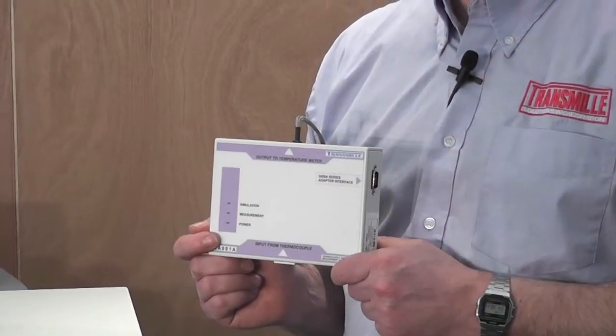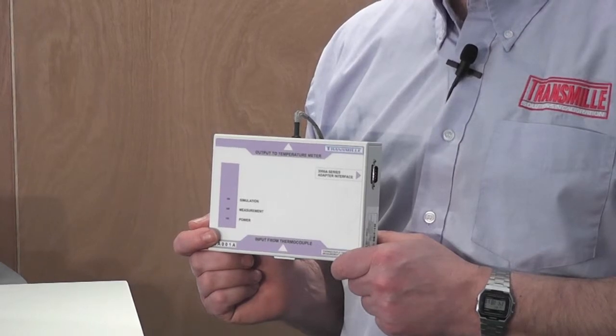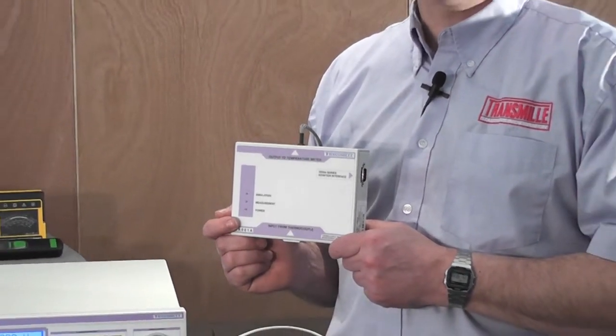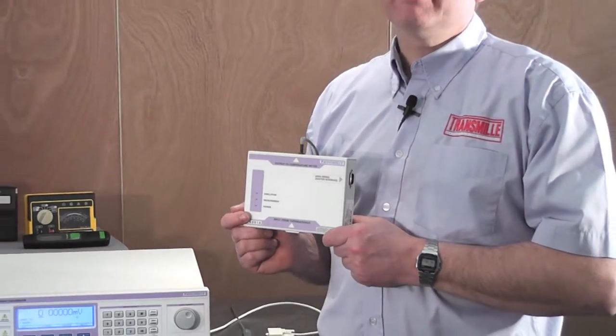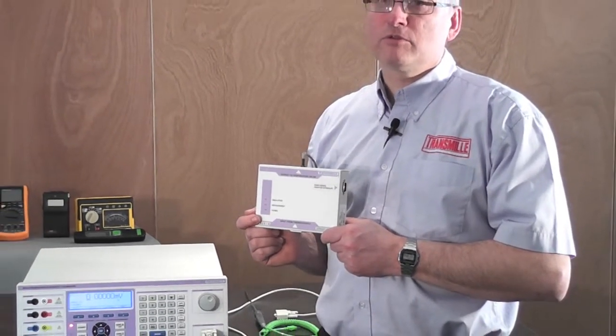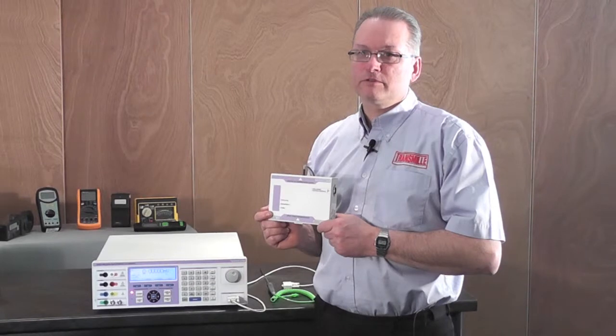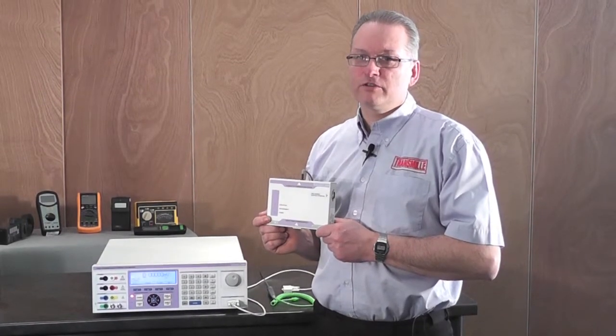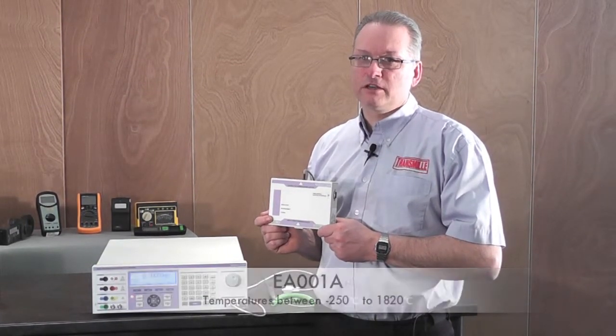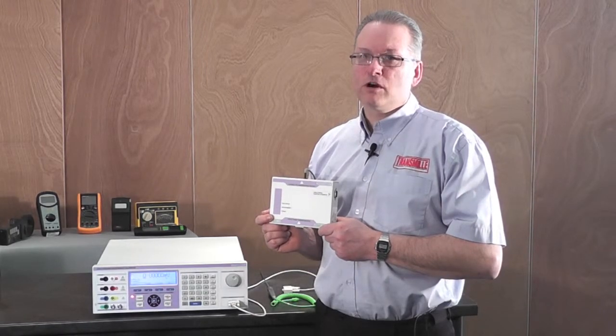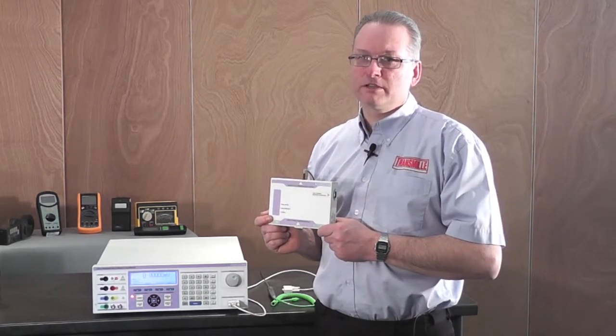The adapter has a high accuracy temperature sensor within the body of the neutral copper connectors. This eliminates the need for multiple thermocouple compensating cables. EA001A can simulate temperatures between minus 250 degrees C up to 1820 degrees C. Automatic and manual cold junction compensation modes can be selected.